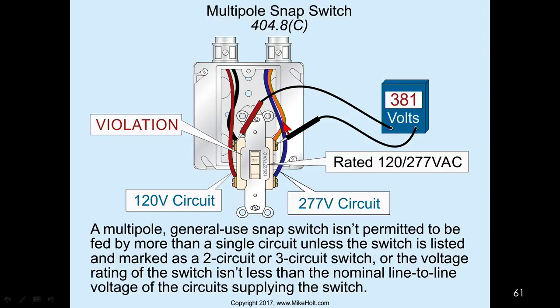Now watch this. This is one circuit. This is another circuit. But then we have a problem, guys. Back on 210.7, it said that anytime you have more than one circuit on a device, you had to simultaneously open that device. So you can never, ever have this application because this is coming out of one panel. This is coming out of another panel, in the case of 120/277 like this here. Or you could not have this one panel A, 120, and another panel B, 120. So this practice has not been permitted for many cycles.